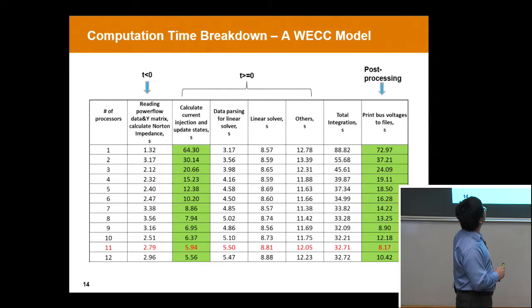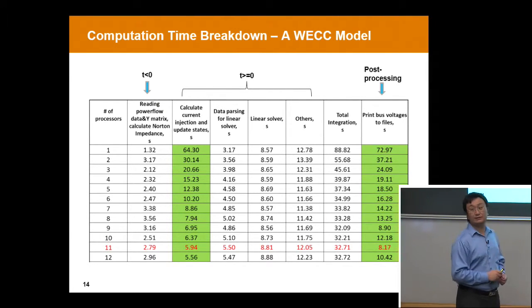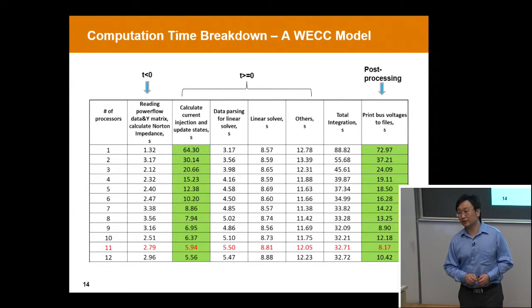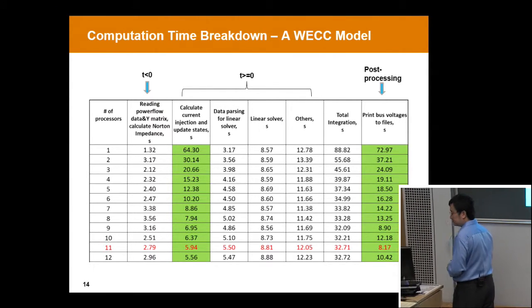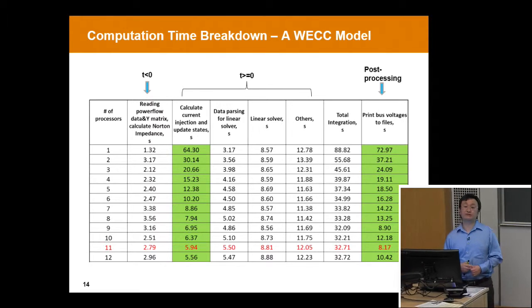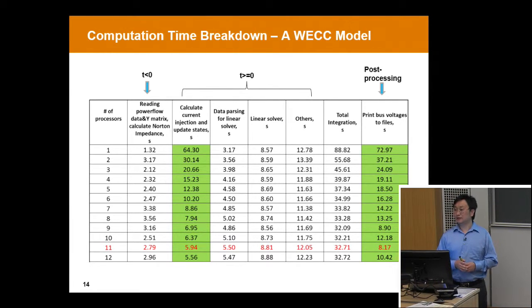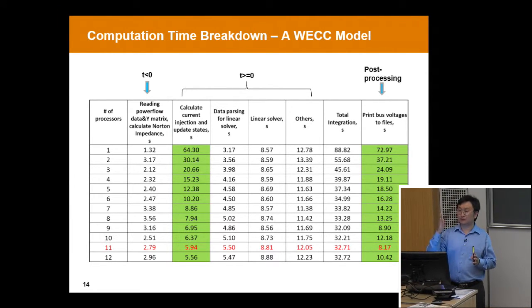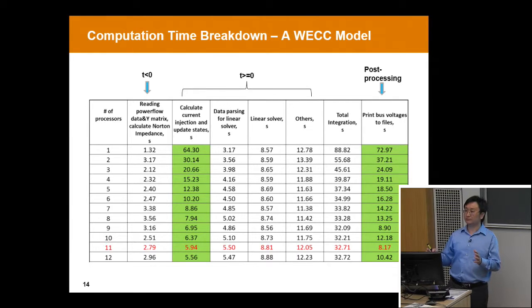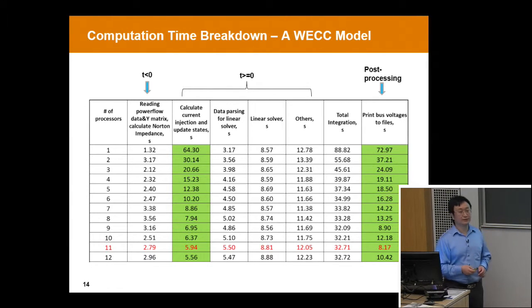The next column shows significant speedup. This includes the current injection calculation, updating states and their derivatives, because different generators do not talk to each other. The only interface between a generator model and the network is through its stator, and normally there's no information passing directly between two generators.